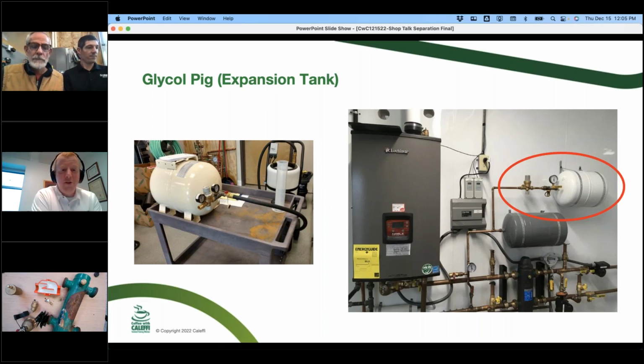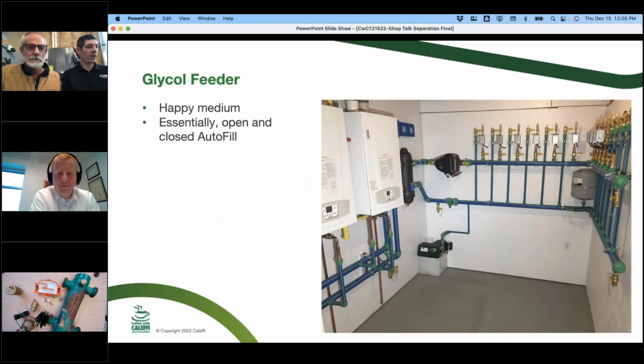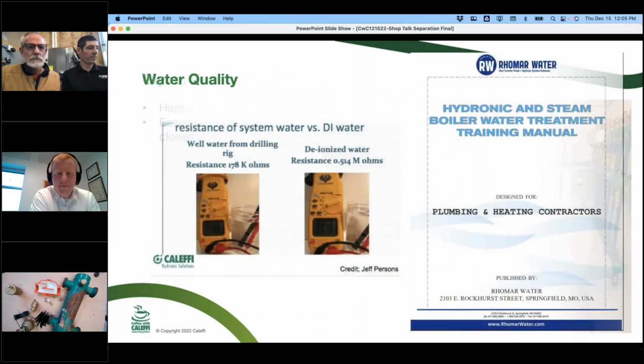So same idea. You're limiting the amount of fresh water that can come in. Put 50 pounds of water pressure in that expansion tank and then put a fill valve on it to regulate it at whatever you want, 12. And now you've got about 3.2 gallons you'll get out of a number 30 expansion tank for backup. And that would be enough to do that cold weather fill.